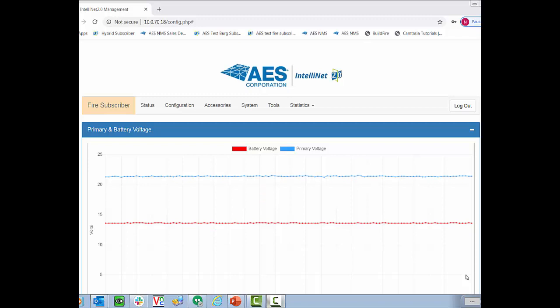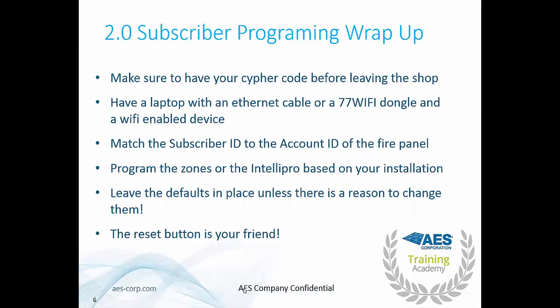All right and that's pretty much everything for AES's 2.0 radio programming. Let's have a little bit of a wrap up. First we want to make sure that you have your Cypher code before leaving the shop. You have a laptop with an ethernet cable or a 77 wi-fi dongle and a wi-fi enabled device. You want to make sure to match the subscriber ID and the account ID of the fire panel. Program the zones or the Intellipro based on your installation. Leave the defaults in place unless there's a reason to change and remember when in doubt the reset button is your friend. Thank you very much. If you have any additional questions about 2.0 subscriber programming please stay tuned for our tech support number. We'll be happy to help. Have a great day.